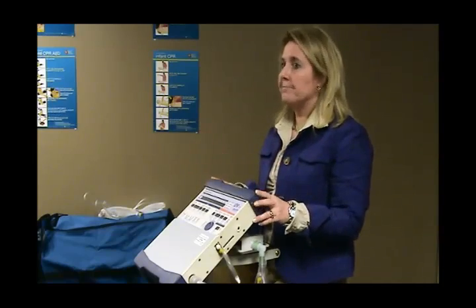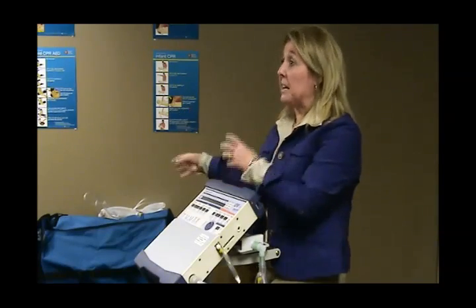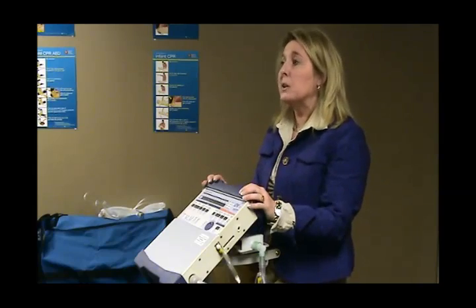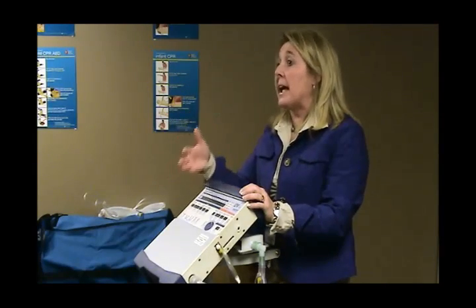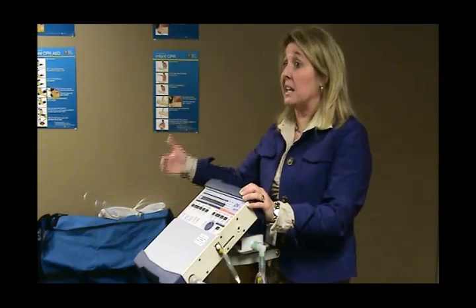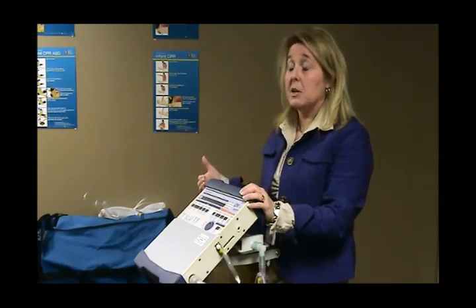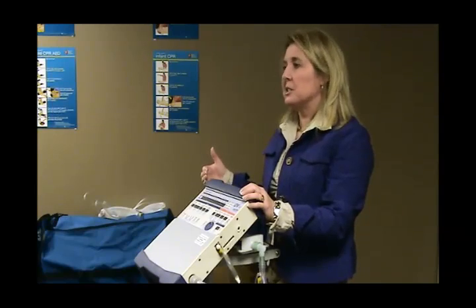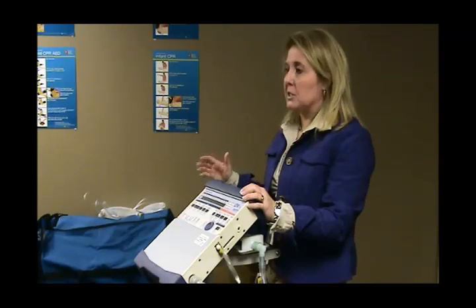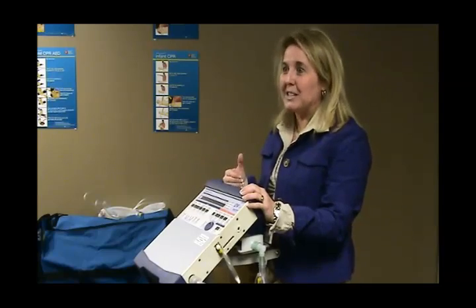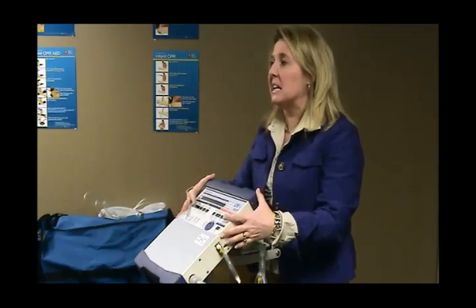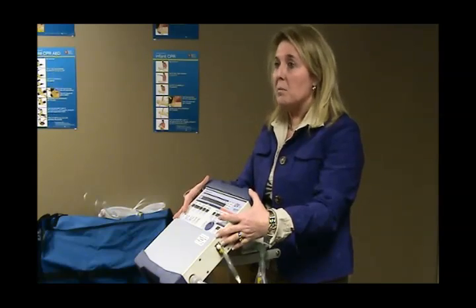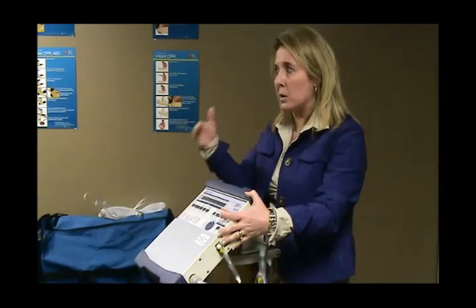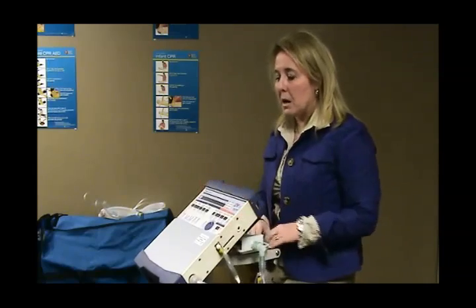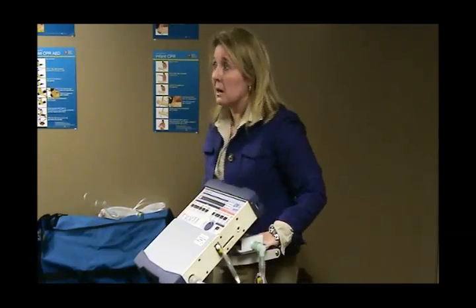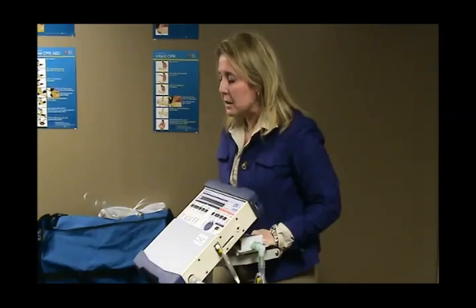All right, but that can be done in the home. Switching manufacturers, whether it's going from somebody else's to ours or vice versa. Because we do have a lot of people who were okay on another type of device when they were non-invasive, then they get trached and try to stay on that device. It is FDA approved for that, so you can use it for that, but the patient is not tolerating it well, for multiple reasons. So then they want to go to the LTV, because this is more of an ICU style vent. I don't recommend that in the home. That needs to happen in the hospital so that we can track what's going on with the person. So that's when I would recommend a hospitalization for transition.